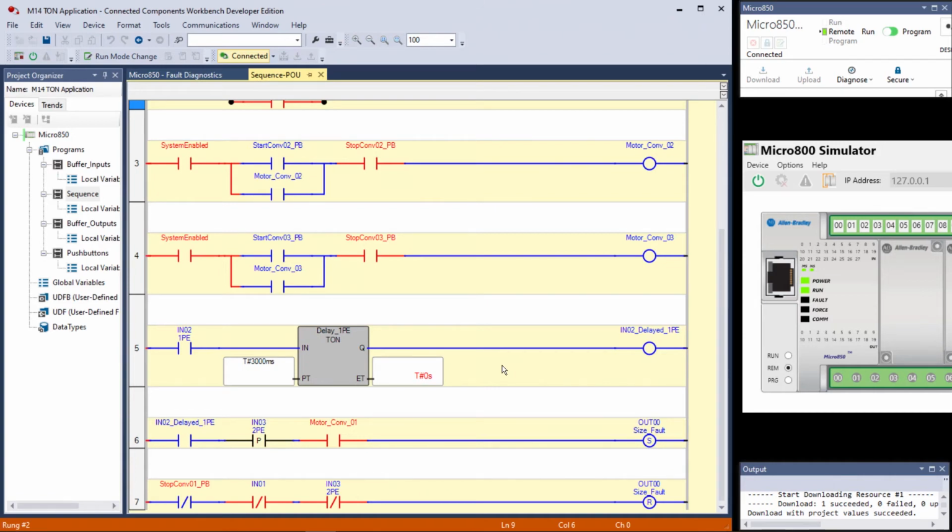If that were the case, without photo eye 1 being blocked, we wouldn't get a fault anyway, because remember that with this rising edge true if on in our rung 6, the train's left the station after one scan of 2 PE being blocked. So all this does is delays whether or not it considers 1 PE on. So if somebody walks by and just runs their fingers through there, this is what you're going to see. You just see a little burst of time, but it never times out. They'd have to have their fingers in there for longer than 3 seconds.